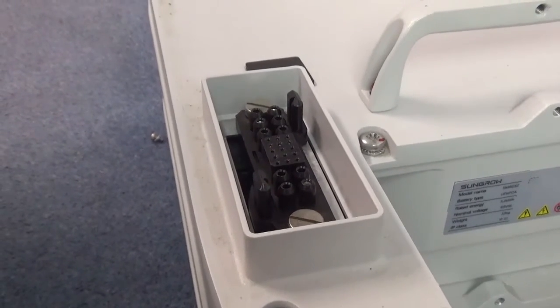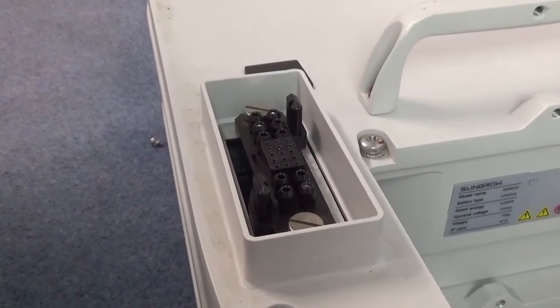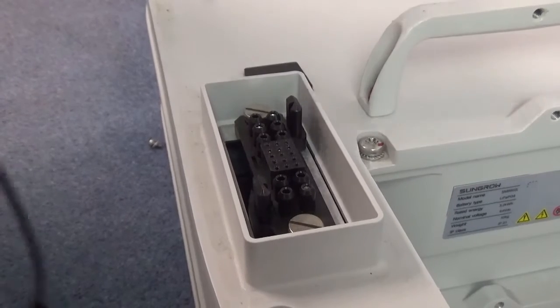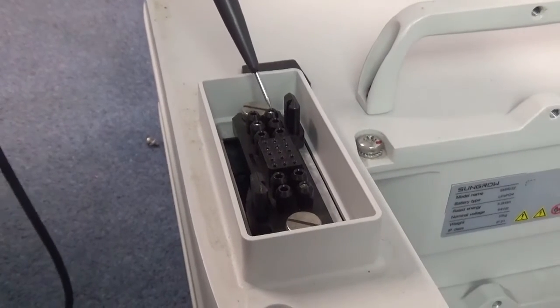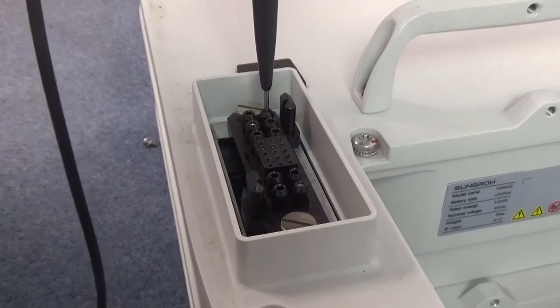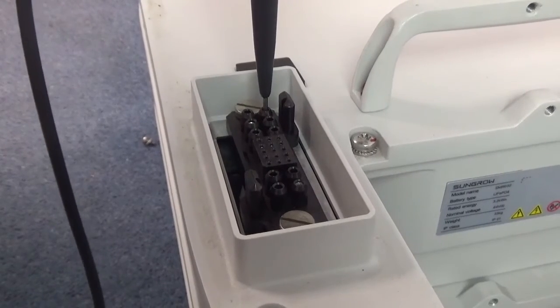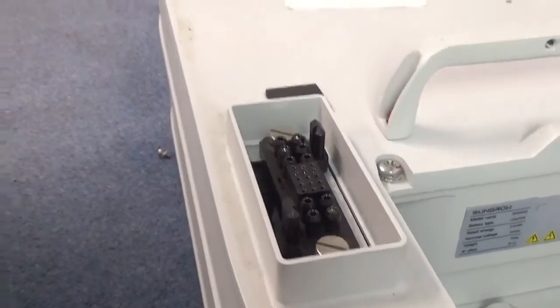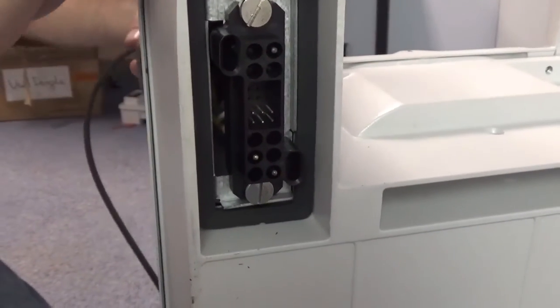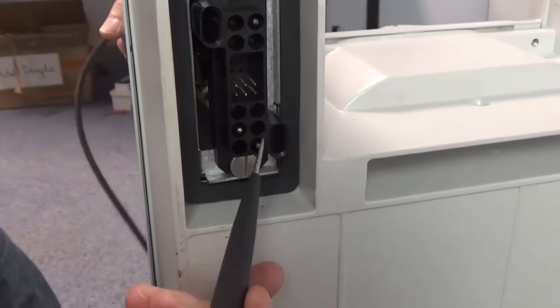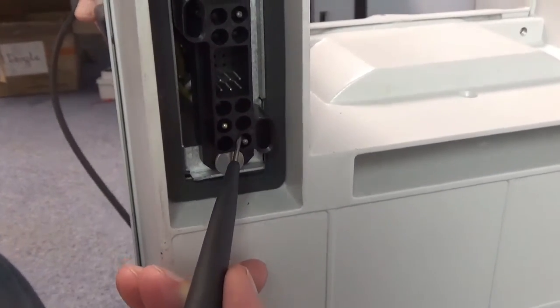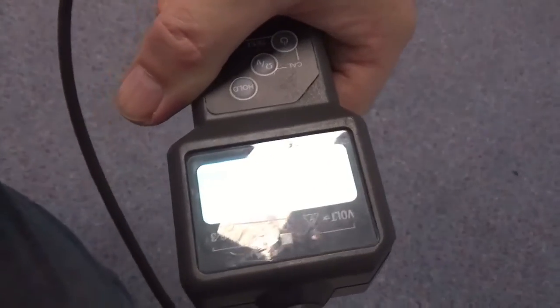Now I'm going to read the module battery level, the voltage level. I have a module here taken off. I'm going to show you the positive terminal is this one here, the rear left hand side terminal. I'm going to move over to this module here which has been taken off. I'm going to go into that rear left hand side and directly below it is the negative terminal. I'm measuring 65.6 volts which is okay. However, if the voltage was too low or not there at all, we know the module is faulty.